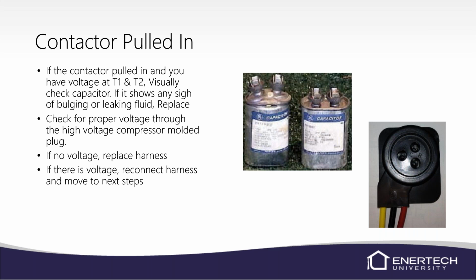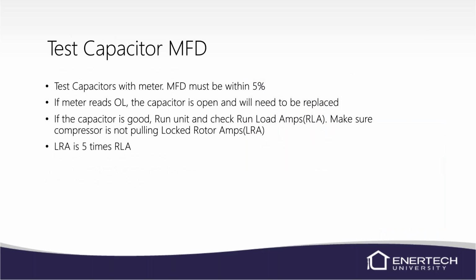Make sure you check the high voltage harness on the compressor and make sure you've got voltage in through the plug there. There could be something wrong internally in the plug, so make sure you've got voltage there. If you do have voltage, go ahead and reconnect the harness and we'll move on to the next step. Obviously, test your capacitor. If the meter reads OL, the capacitor is open and will need to be replaced. If the capacitor is good, run the unit and check run load amps.